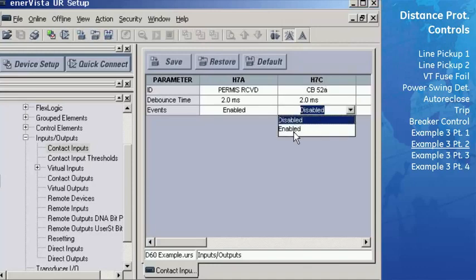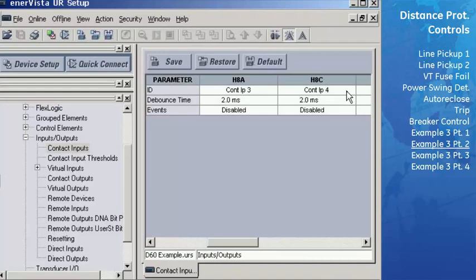Set the Events field to Enabled. Change the name of H8C to Auto Reclose Enabled, which will enable the recloser function. Set the Events field to Enabled. Change contact H7A to circuit breaker ready, which is an indication that the breaker is ready. Set the events field to enabled.